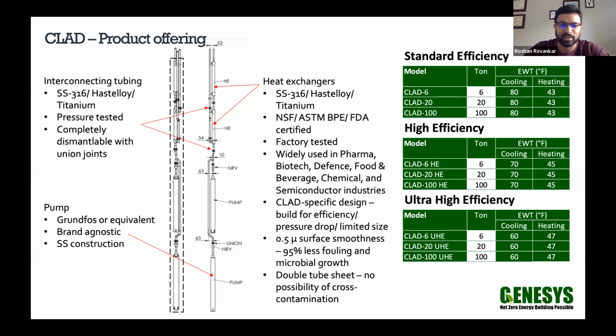If you can imagine, there will be turbulent flow within these heat exchangers, and with such a smooth finish, there is no microbial growth happening on the heat exchangers themselves. It is meant to operate in harsh water conditions and also in conditions where typical heat exchangers would foul. But the advantage of the smooth surface is that fouling is reduced drastically.